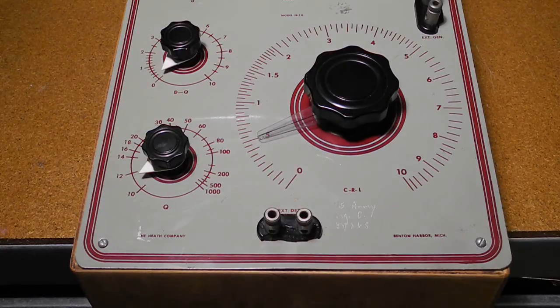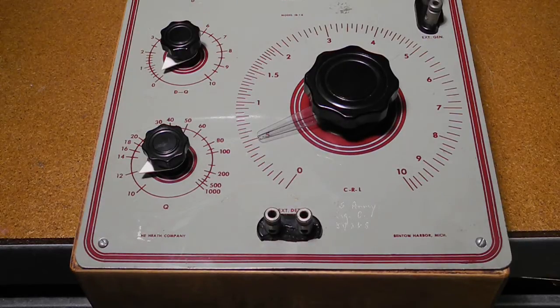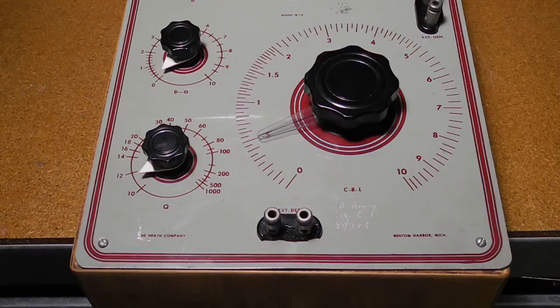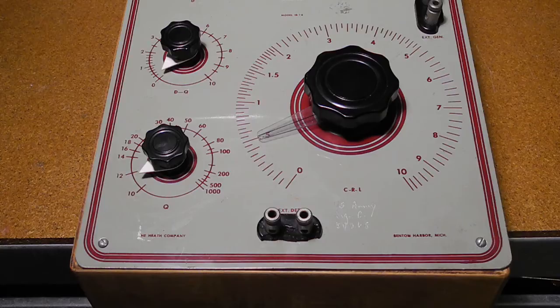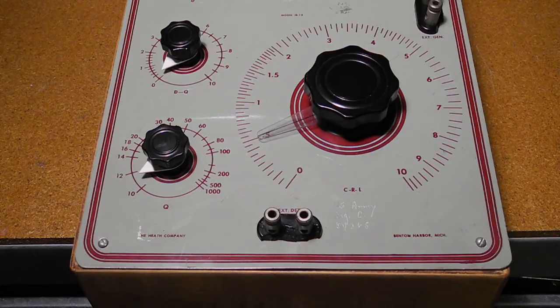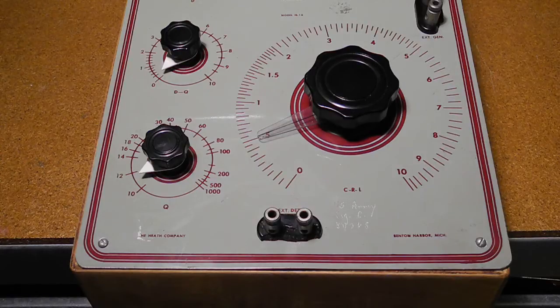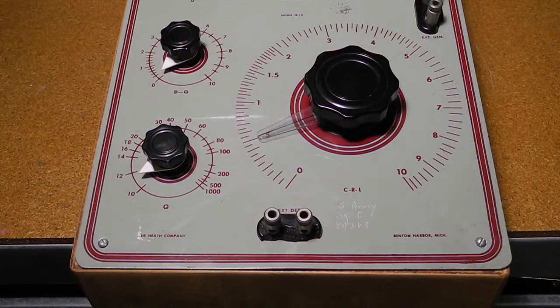It can measure resistance from 10 milliohms to 10 megaohms, capacitance from 10 picofarads to 100 microfarads, and inductance from 10 microhenries to 100 henries. Eight ranges are provided. It also measures Q of inductors from 1 to 1000, and dissipation factor of capacitors from 0.002 to 1. Accuracy is about plus or minus 3% for resistance and capacitance, and plus or minus 10% for inductance.